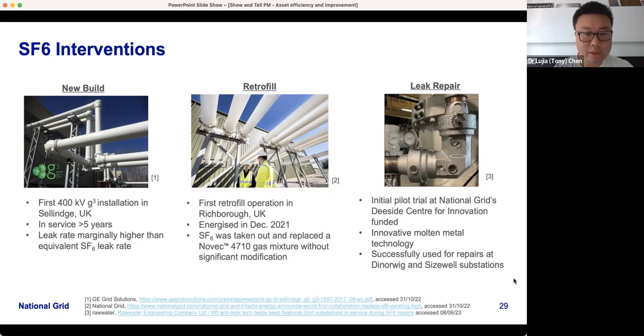So literally gas out, new gas in. We'll have to change the density meter and also make some small modification to the desiccant, which doesn't require opening the bus bars, which would then become quite costly. The first retrofill operation in the world was accomplished in the UK, in Richborough, Kent, by National Grid, and was energized in December 2021. So still early days for these two solutions.